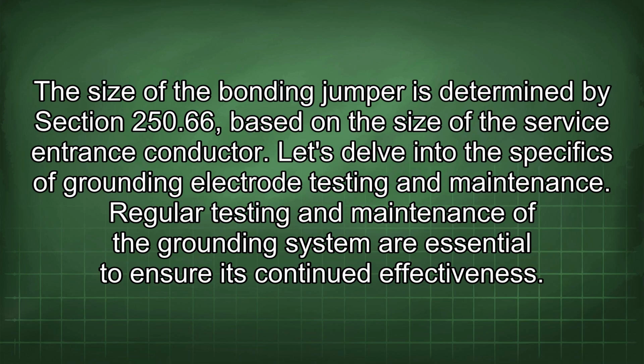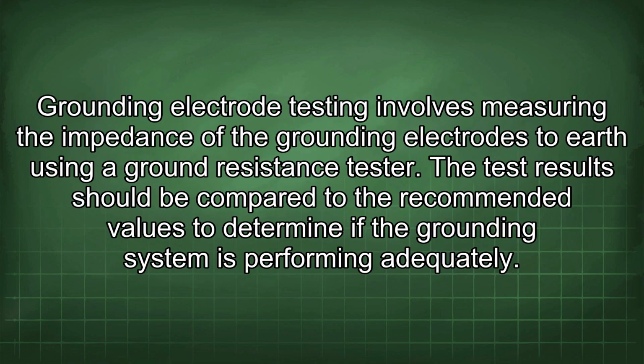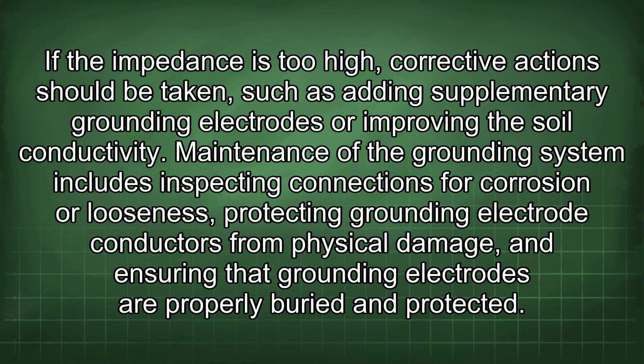Let's delve into the specifics of grounding electrode testing and maintenance. Regular testing and maintenance of the grounding system are essential to ensure its continued effectiveness. Grounding electrode testing involves measuring the impedance of the grounding electrodes to earth using a ground resistance tester. Test results should be compared to the recommended values to determine if the grounding system is performing adequately. If the impedance is too high, corrective action should be taken, such as adding supplementary grounding electrodes or improving the soil conductivity. Maintenance of the grounding system includes inspecting connections for corrosion or looseness, protecting grounding electrode conductors from physical damage, and ensuring that grounding electrodes are properly buried and protected.